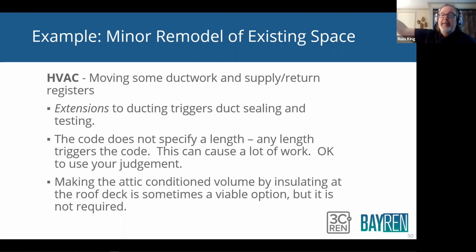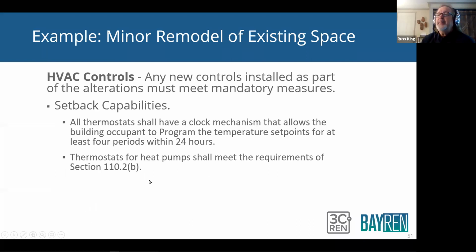Well, guess what? That not only improved their thermal boundary, but it made all the ducts inside conditioned space. They didn't have to seal them, okay? Because that leak is going to conditioned space. The building was way more comfortable after they did that, by the way. Their loads dropped dramatically by doing that. So it's an option. It's an option. Just be aware of that.